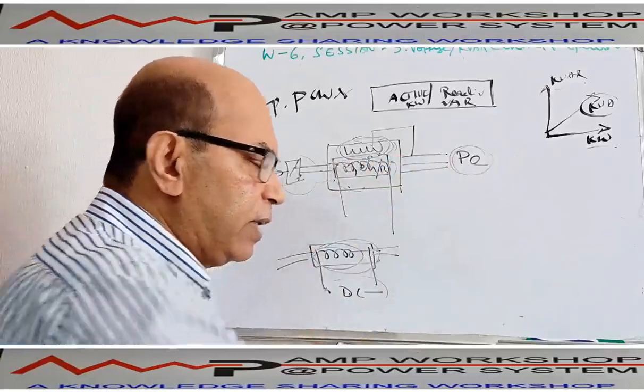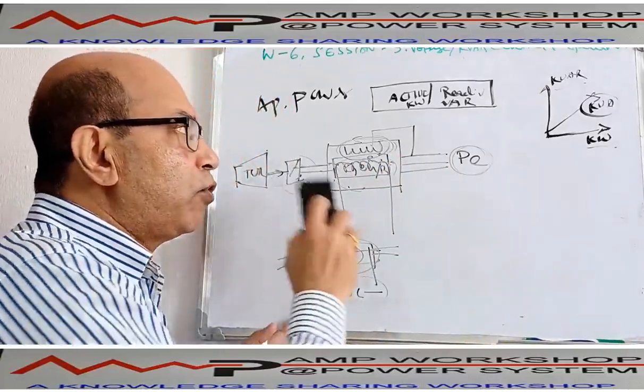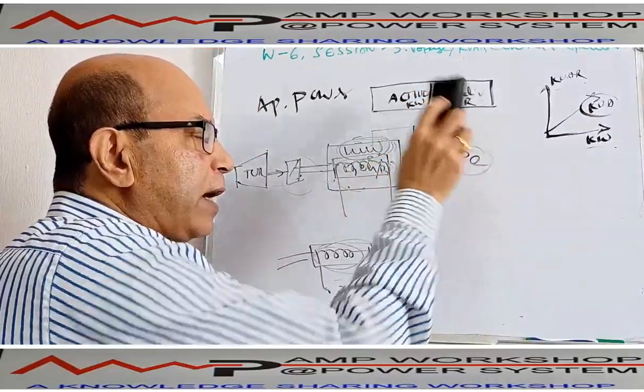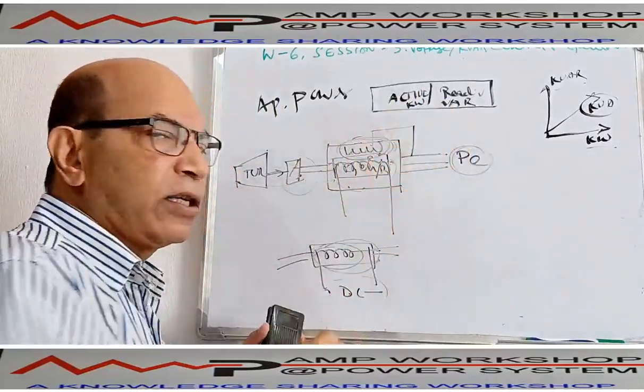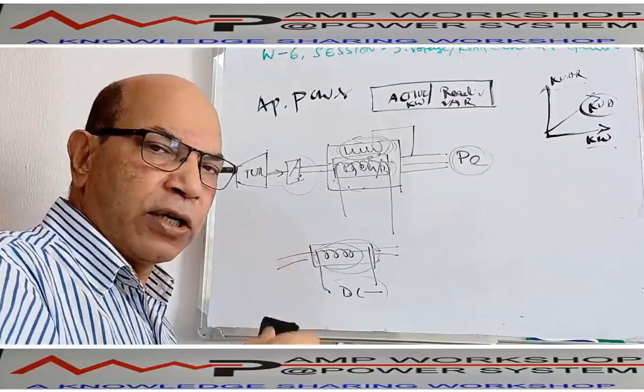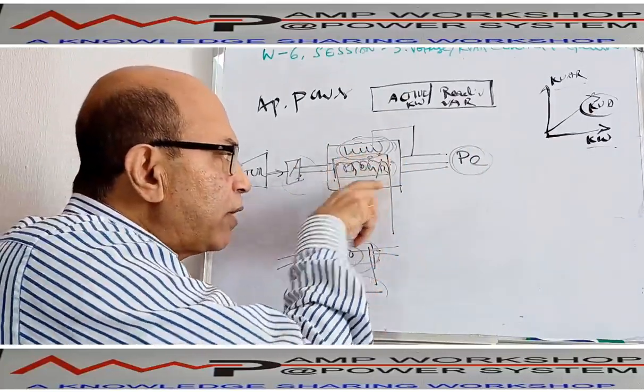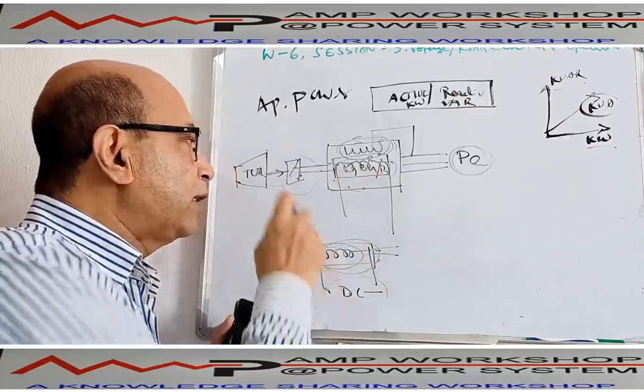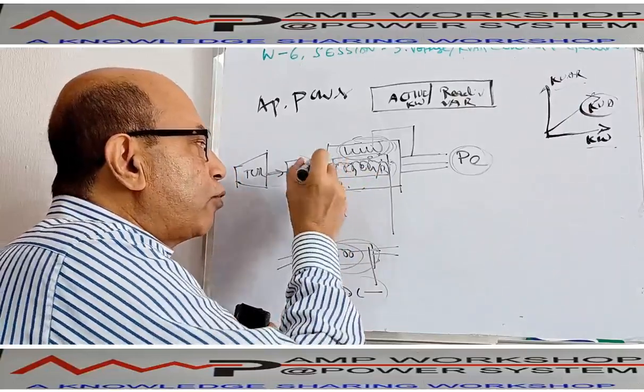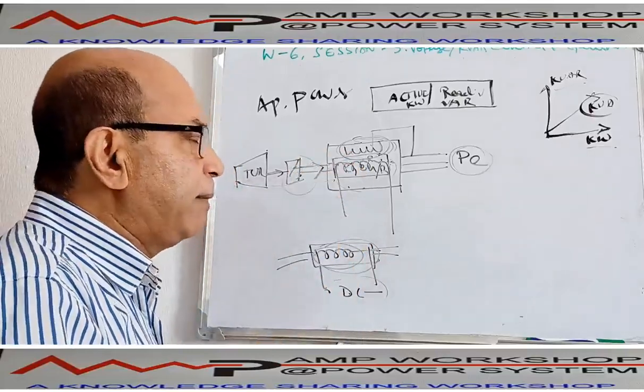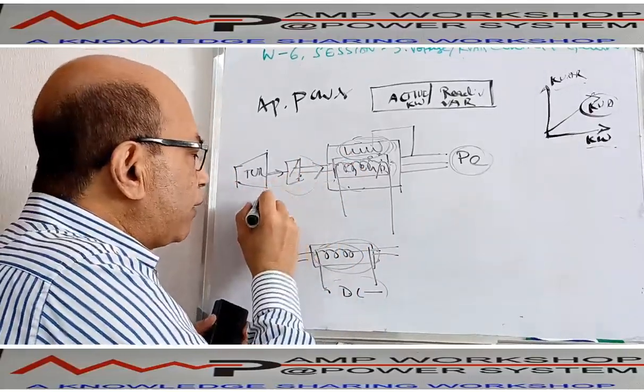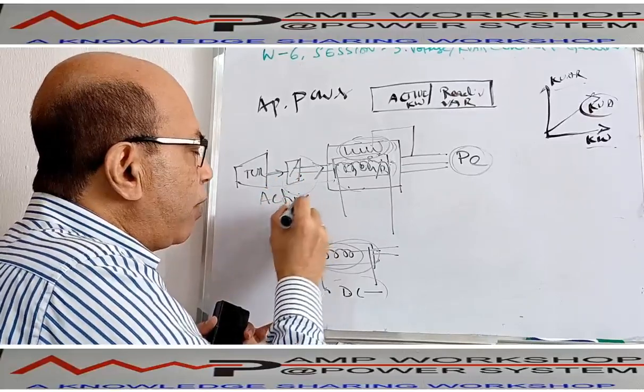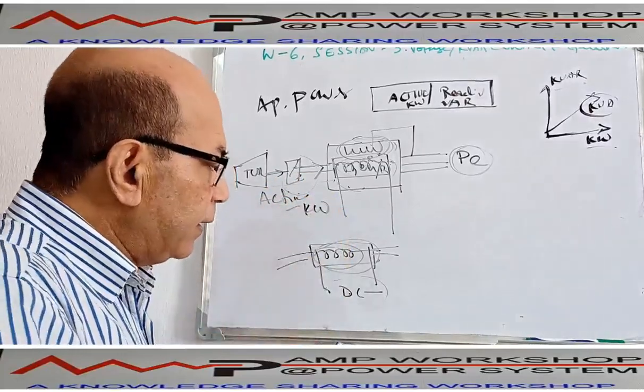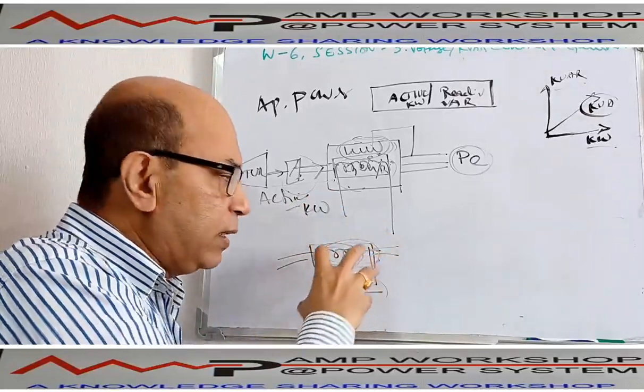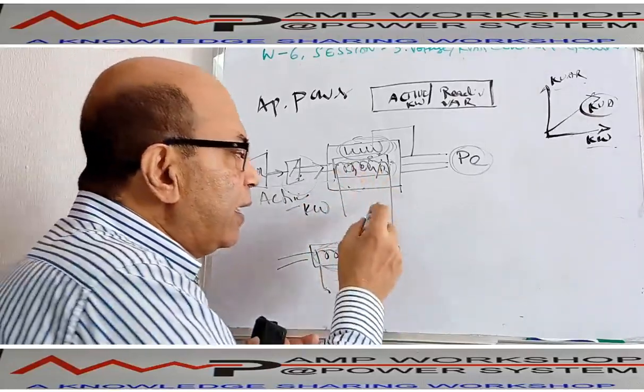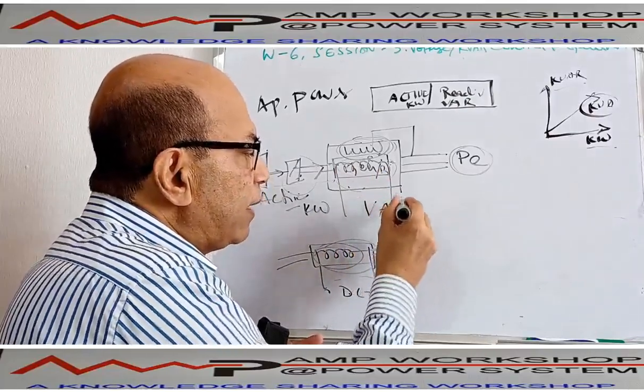That means when an electrical generator is producing power, it produces two types of power. One is active power and another is reactive power. Now the rotational part is called active power. When the rotor is rotating, who is rotating it? The turbine. So the turbine is giving the mechanical power to rotate the rotor, and that is what we call the active power. So the turbine is responsible for the active power, the kilowatt. And this rotor is producing the magnetic field, and that is giving your reactive part. The VAR is produced by the rotor.